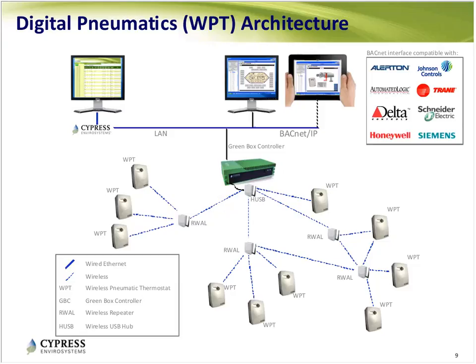So really, for your building automation system, it looks like a digital stat. It's a BACnet device, and it's quite easy to deal with. Pretty much, it's like if you bought a Johnson stat for a Johnson Metasys system - it would just connect right in. That's what these are designed to look like, and about 2/3 of our customers use the BACnet interface to communicate and control the WPT, the wireless pneumatic thermostat.